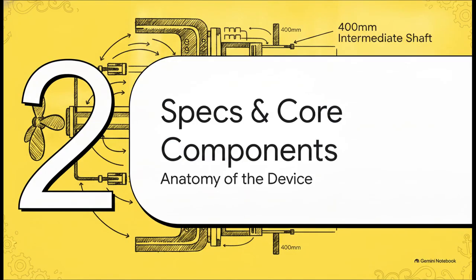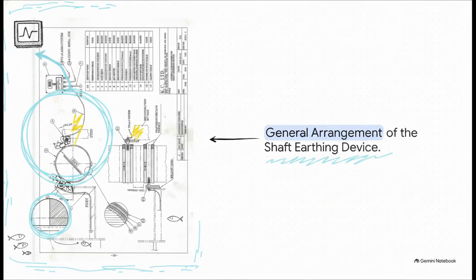Now that we understand the why, let's look at part 2, specifications and core components. Now, what's really interesting about this layout is how clearly the whole mechanical architecture is structured. Imagine anchoring your eyes to that large 400mm intermediate shaft right in the center. Notice how it's wrapped tightly by a silver alloy slip ring? Then, riding directly on that ring, you've got the brush holders. There's a double brush holder on one side, purely for earthing, and a single brush holder on the other, specifically designed for monitoring. If you follow the wiring path all the way up from that monitoring brush, the system connects straight to a digital millivolt meter, giving the crew a real-time window into the electrical state of the shaft.